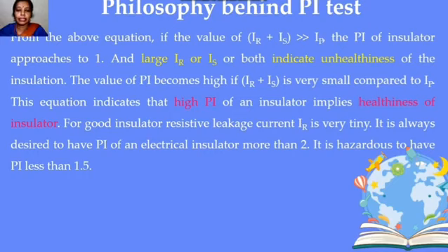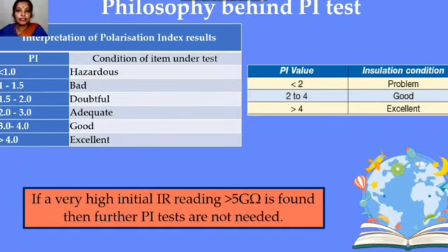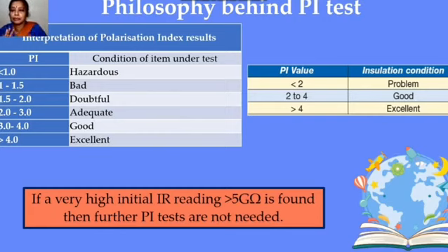It is desirable to have a PI greater than 2; it is hazardous to have a PI less than 1.5. The interpretation: PI less than 1 is hazardous and the equipment should be replaced; 1 to 1.5 is bad; 1.5 to 2 is doubtful; 2 to 3 is adequate; 3 to 4 is good; above 4 is excellent. Summarized: less than 2 indicates a problem; 2 to 4 is good condition; greater than 4 is excellent and no maintenance is needed. If initial IR reading is greater than 5 gigaohms, PI testing is not necessary.